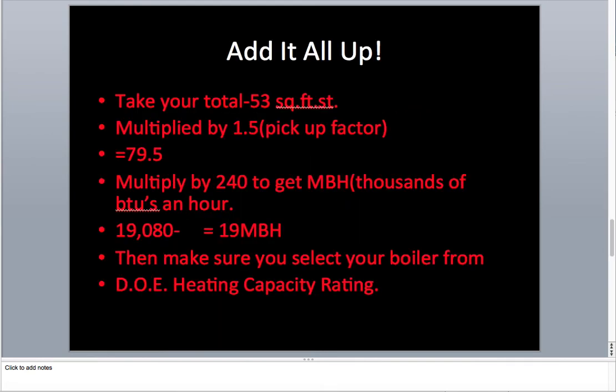So you add it all up. You take your total square feet of steam, which is 53, multiply by 1.5. That's your pickup factor. This is the variable I was talking about earlier as far as things changing over the years. Use this pickup factor. Here's your total. 53 times 1.5. And then you want to multiply it by 240 to get your MBH, a thousand BTUs an hour. That's 19,080, down to 19 MBH.